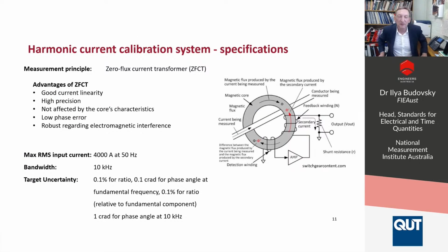After some thinking, we chose the zero flux current transformer as the main measuring unit for our system. The way the zero flux current transformer works is that the measured current flowing through the magnetic core creates flux, which is measured by a detector winding, which creates a certain signal on the secondary winding that provides the same flux in the opposite direction, and leads to zero flux in the core. Therefore the signal of the secondary winding can be the output of the device.